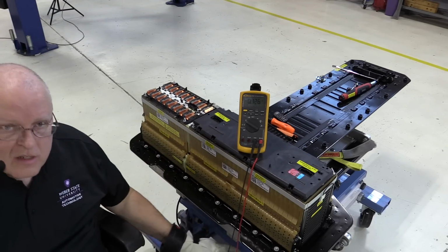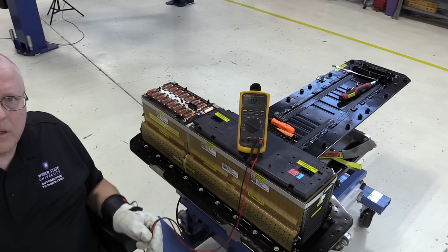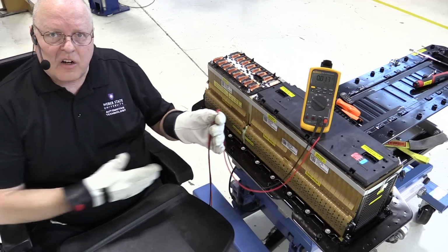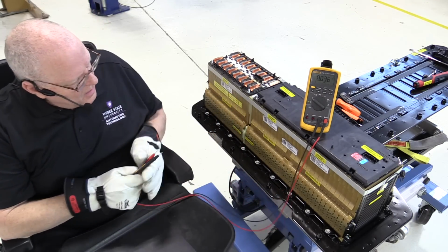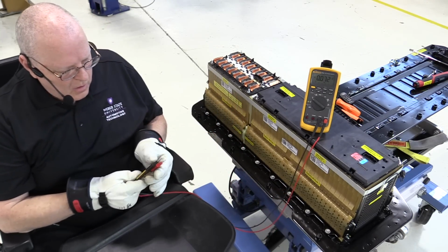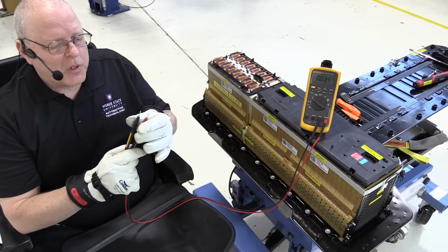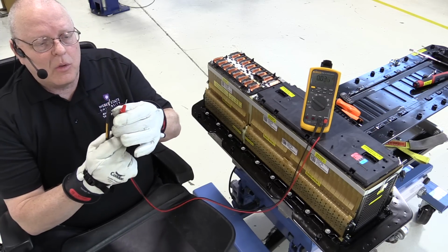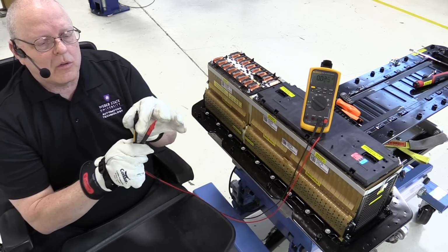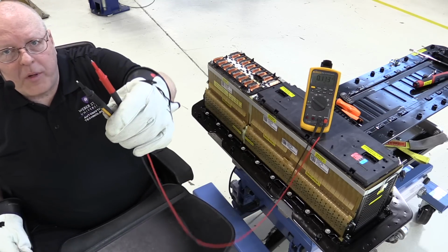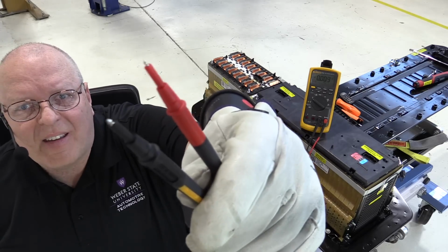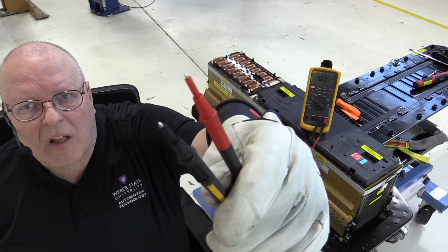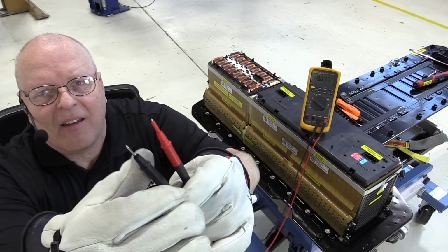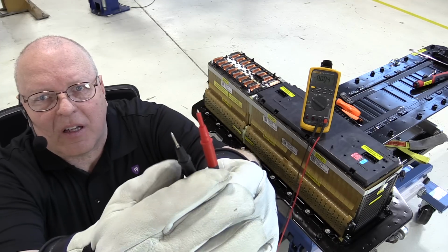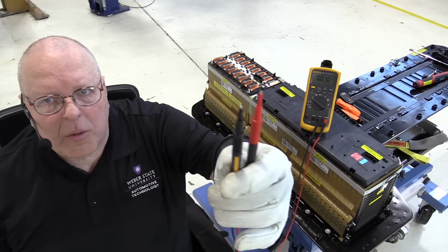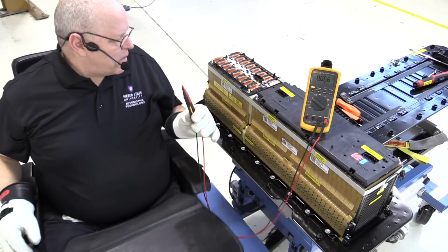The meter I'm using is a Fluke 87 Series 5 multimeter, set on DC volts. This is a Class 3 multimeter with Class 3 probes. They can be Class 2 or Class 3 depending on which direction you twist the probe tip. In this configuration, they're Class 3; in that configuration, it's Class 2. We're supposed to use Class 3 on these high voltage batteries.